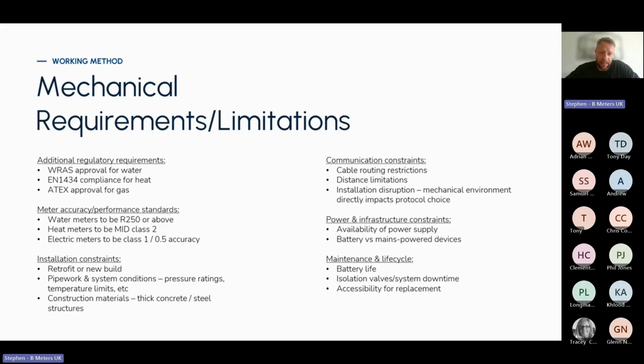Meter accuracy, performance, and standards - does a consultant or client request a certain standard? For example, they could say water meters need to be R250 or above, although I doubt a client would request that; it's more so for monitoring low flow rates. Heat meters, as we've touched on, are typically MID class 2. There are MID class 3 meters out there which are less accurate, but they don't tend to be considered in a lot of instances anyway. Same with electricity meters - is it class 1 or 0.5?